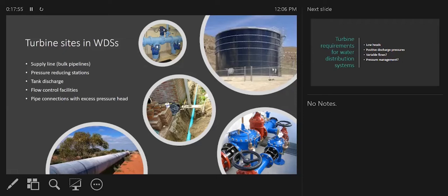The second is pressure reducing stations. In order to maintain target pressure at different places in the network, it's necessary to bleed off a lot of the energy in the head so you don't have excessively high pressures, which damage pipes and other infrastructure. Right now that energy is essentially wasted, so much of the literature on energy recovery turbines in water distribution systems focuses on pressure reducing valve replacement to harvest that wasted energy.